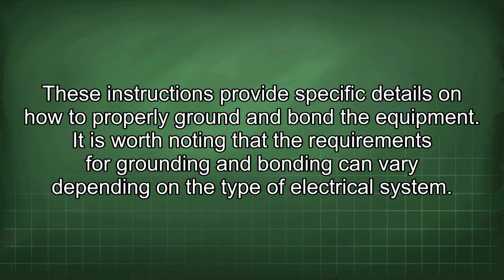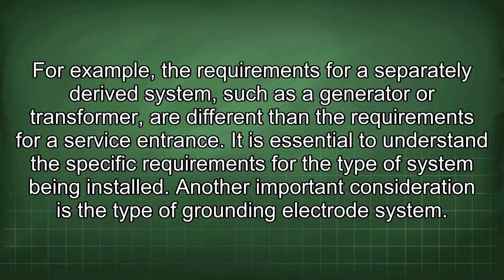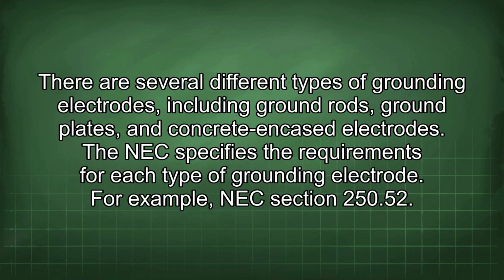It is worth noting that the requirements for grounding and bonding can vary depending on the type of electrical system. For example, the requirements for a separately derived system, such as a generator or transformer, are different than the requirements for a service entrance. It is essential to understand the specific requirements for the type of system being installed. Another important consideration is the type of grounding electrode system. There are several different types of grounding electrodes, including ground rods, ground plates, and concrete encased electrodes. The NEC specifies the requirements for each type of grounding electrode.